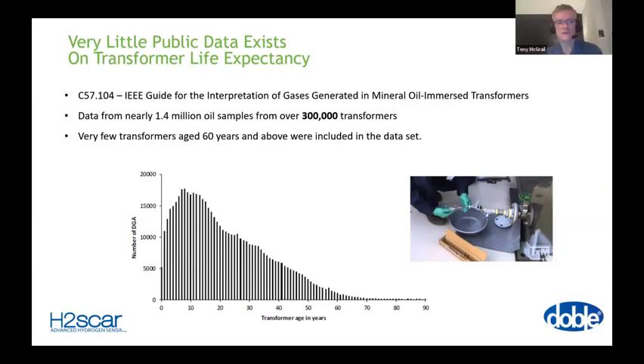Yeah, sure. So this is an interesting chart in that it doesn't tell you anything about how many have failed. It only tells you the age of a unit in service. It doesn't tell you how long it lasted after that. It doesn't tell you if we've had 100 samples taken from a transformer. It just gives you an indication that there are fewer samples from older transformers, therefore older transformers are less likely to occur, which is what pretty much you'd expect.